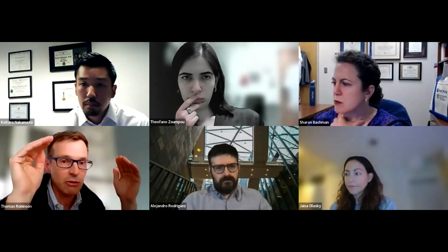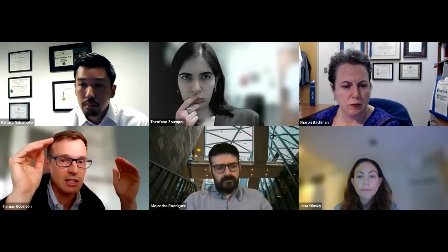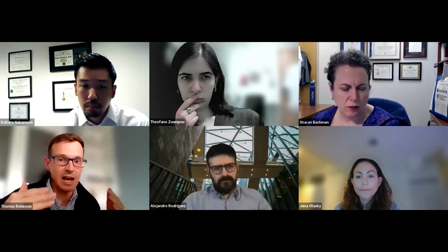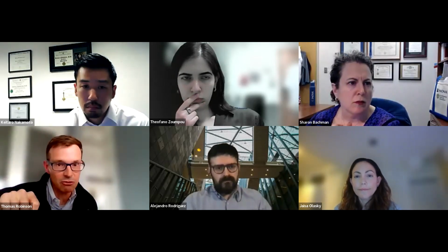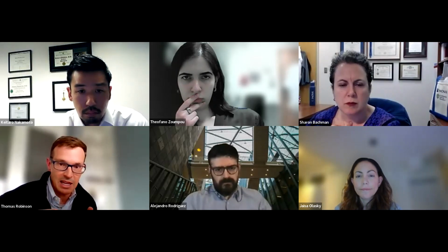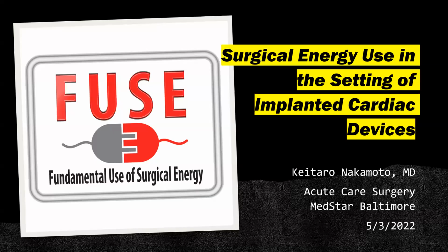When we talk about the ultrasonic device, it's a vibration. You have the piezoelectric electrode that plugs into the back of the handpiece. The scrub tech or nurse setting up your instrument has to tighten it to a certain tightness using a little tightening device, because you're seating the extending rod into the piezoelectric electrode to make that rod vibrate.